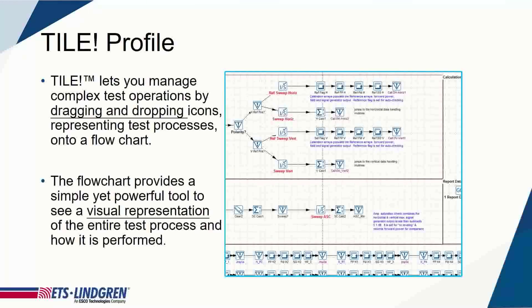Inside the TILE profile, you can manage complex operations. You can drop icons out of what we call the palette into the flowchart — we call them actions. Each action has several hundred, in some places several thousand, lines of code behind it that actually controls everything the action does. What you're doing is opening the properties of the action to input your instruments, your test data, your test limits, and the different correction factors. The bulk of the work is happening in the action itself.